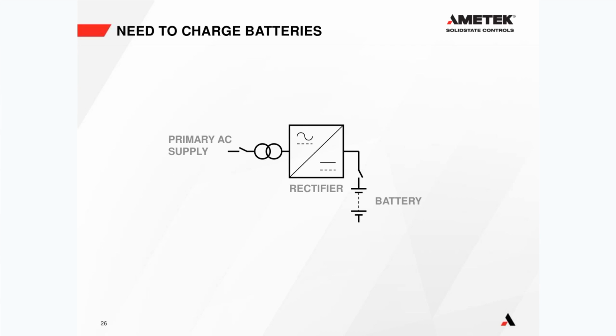The UPS has two main power boxes in it. The first one is on the input, and that is the rectifier or charger. It takes the primary AC from the grid - in truth you could think of it as plugging into your wall socket, although for most industrial systems it's three-phase 480, not 120 out of the wall. That goes into the rectifier box, which takes the AC and changes it into DC, and that charges the battery.